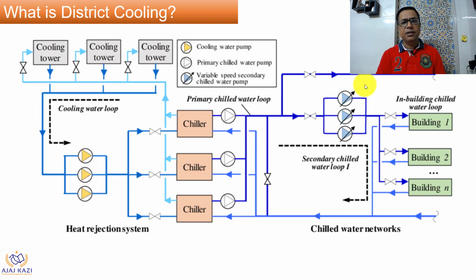In a schematic, again, you can have chillers and a pumping system. Chillers are generally connected to a cooling tower, and if it's a water-cooled system, there are pumps for the cooling tower. Then there are secondary networking pumps, and each building will have its own energy transfer station catering to building 1, building 2, building 3, and so on. The main component which supplies the cold water is pipes, so chilled water pipes are used.